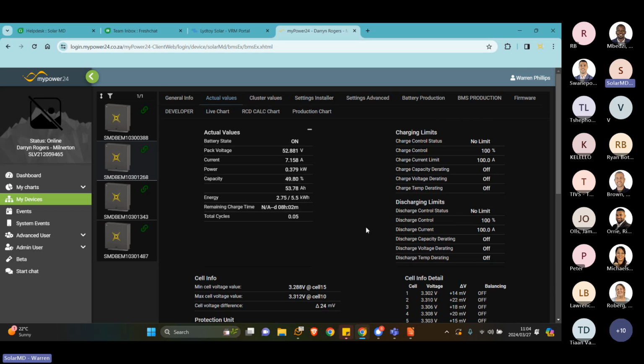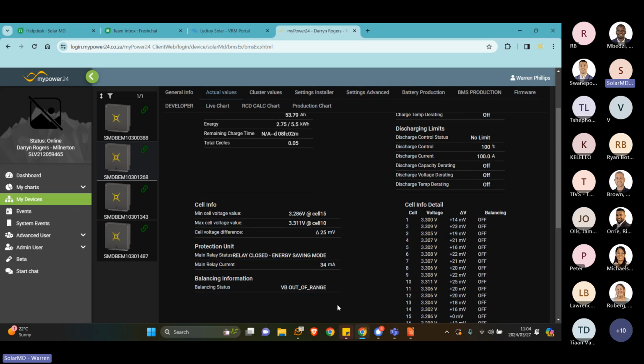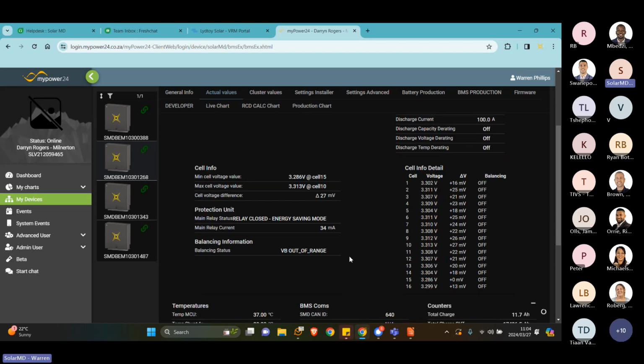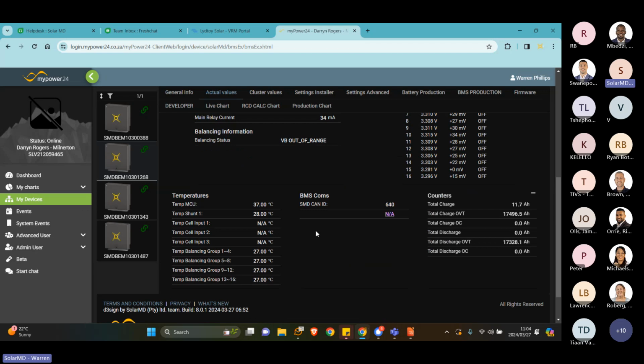You can see the current state of charge, the current limits, the minimum and maximum cell voltages, and the status of the relay as to whether it's open or closed. On the right-hand side you can see the cell voltages, and the temperature of the BMS itself, as well as the temperature of the circuits that balance the cells. In some cases, with some batteries, they have multiple external temperature sensors inside the battery pack, and those values would be on the BMS and recorded there as well.